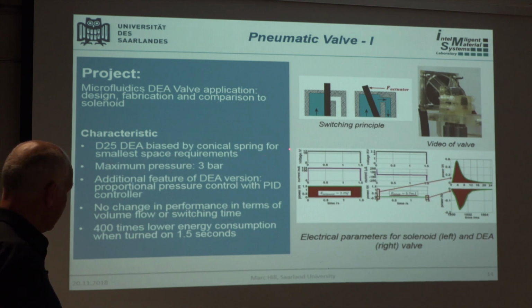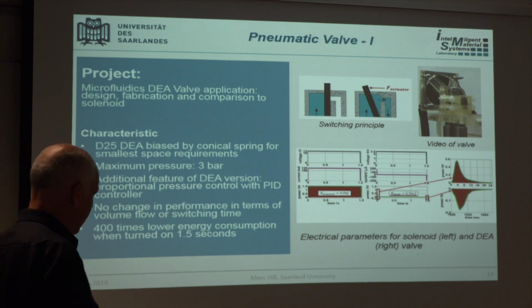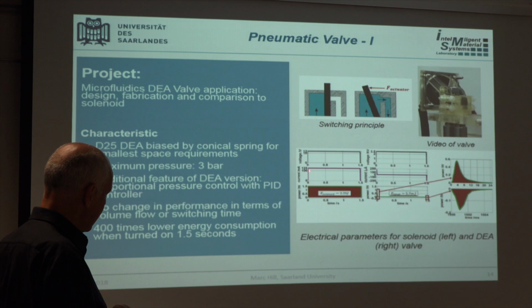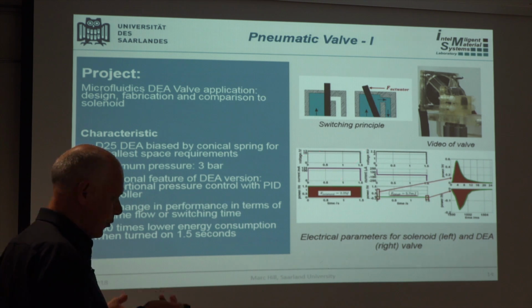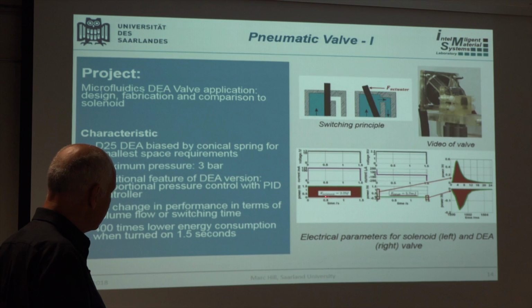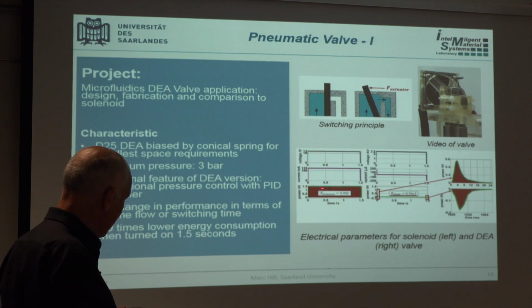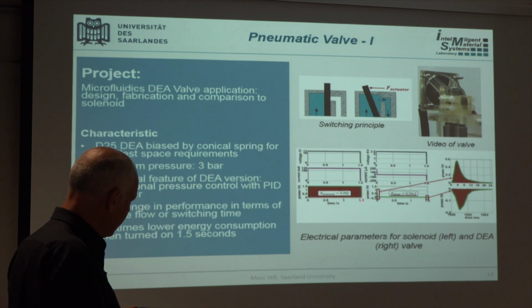Putting it together, we found huge potential for energy conservation. We looked at a process opening the valve for a second and a half, then closing it again. With a solenoid you must apply constant current: 1.5 watts over 1.5 seconds gives an energy consumption of 2.25 joules.